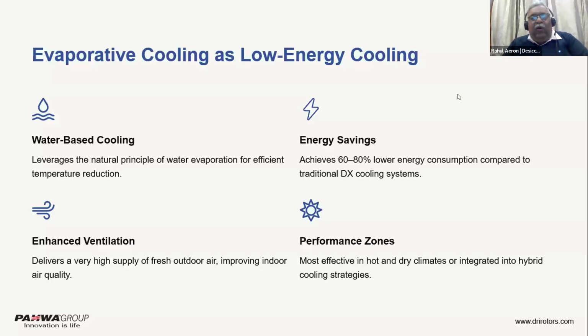It's the best low energy cooling technology which can be used very well in today's buildings, especially naturally ventilated buildings. What are the advantages? It's a water-based cooling, so there is no harmful chemical and no harmful refrigerant. It's a 100% fresh air system. It's an enhanced ventilation system. There are no issues about indoor air quality, because in an air conditioned space you have a lot of recirculation of air, and indoor air quality is always a challenge. Because of this 100% fresh air system, the indoor air quality is taken care of.